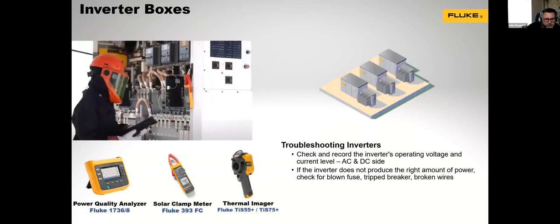So let's look at inverter boxes. Again, we're looking at clamp meters, thermal imagers, and power quality for this. Check and record the inverter's operating voltage and current level. If the inverter does not produce the right amount of power, check for blown fuse, trip breaker, and broken wire. And remember, something that we haven't necessarily put into this presentation is that you should always use your eyes. And again, when we're talking about high voltages, we always recommend that correct PPE is worn, because testing live is under the HSE working live as well.